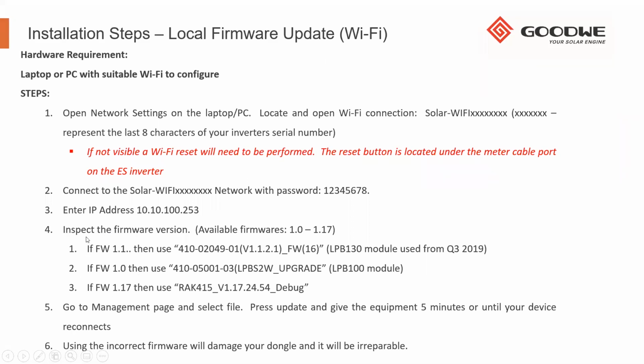Currently, we have 3 firmware versions available. The oldest being the rack, that will most likely only be on 2016, 2017 inverters. Then we've got the slightly newer one, which we used until Q3 in 2019. So just pay quite some attention to the actual current firmware. So the new one, you'll see version 1.1. It'll be either 1.1, 1.2. Then we'll know it's an LPB 130 module, and that will use the latest LPB firmware.